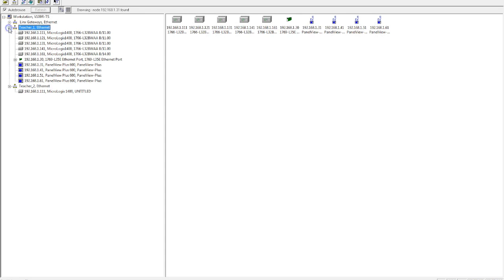Now let's look at the differences between these two types of Ethernet drivers. So my first one that I created went out and searched for every type of PLC, any basically any Rockwell Automation or Allen Bradley product that has an IP address. And it found five MicroLogix 1400s, one CompactLogix L35E, and it found four touchscreens. And inside of this, this will show everything here. This is very good if we want all of these to be networked together.